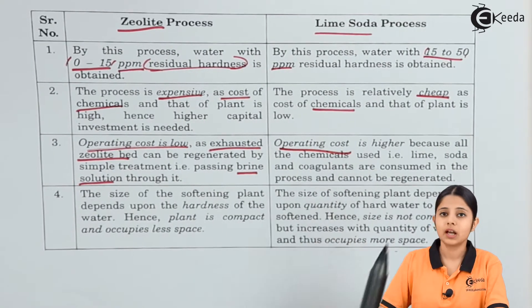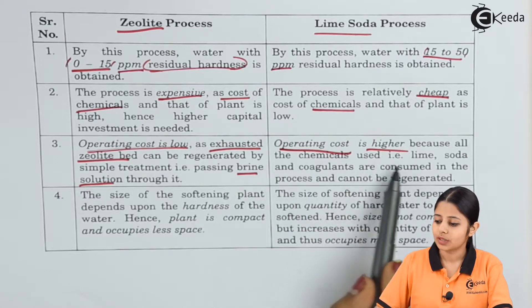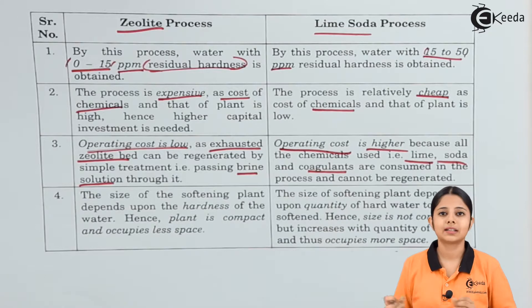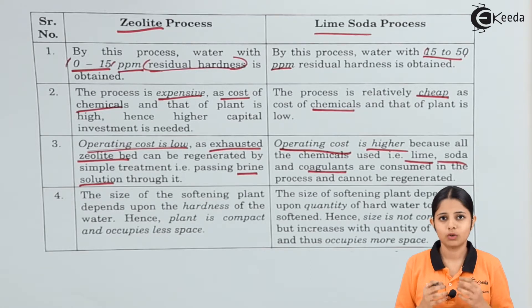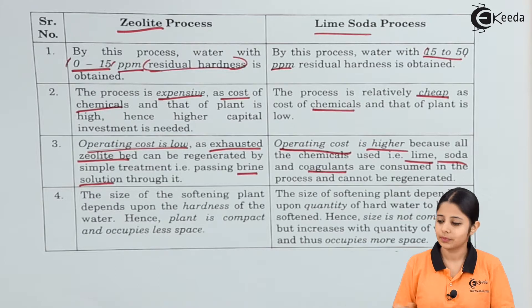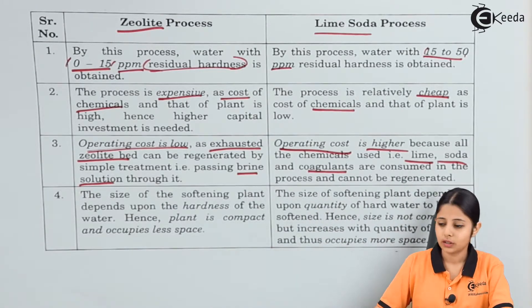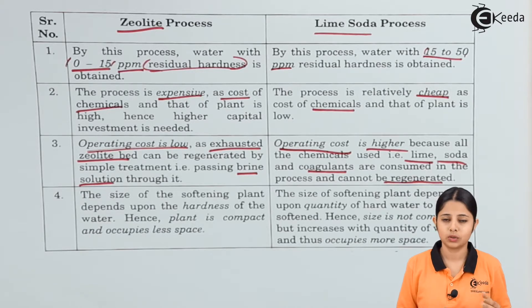In contrast, the operating cost for the lime soda process is higher because all the chemicals used — lime (CaO), soda, and coagulants — are consumed in the process and cannot be regenerated. Coagulants are promoters added to start and accelerate the reaction since the lime soda process does not happen spontaneously. Because lime and soda must be continuously repurchased, the maintenance and operating cost is much higher than for the zeolite process.